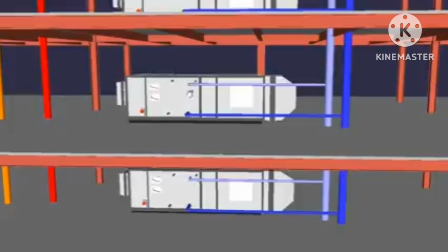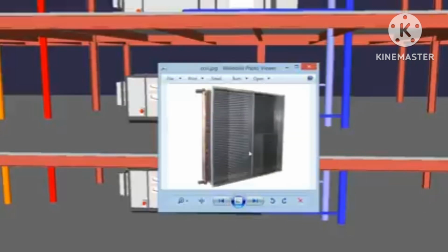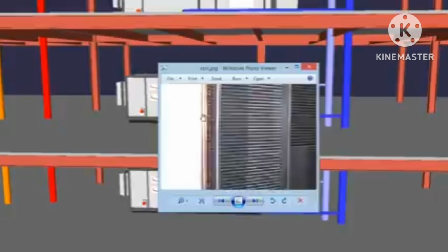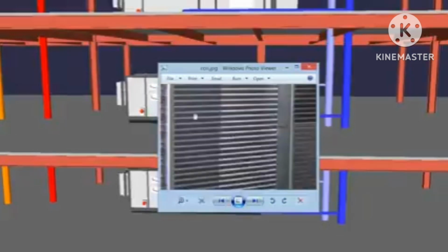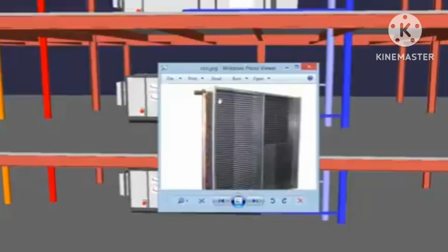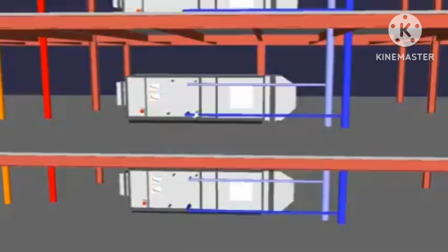And inside this air handling unit is a coil, and the coil will look something like this in the real world, and chilled water enters the coil and makes its way up through all these little loops here, and then back out the top here. So that enters at about 8 degrees in this example, and by the time it reaches the top there, it'll leave that cooling coil at about 14 degrees.